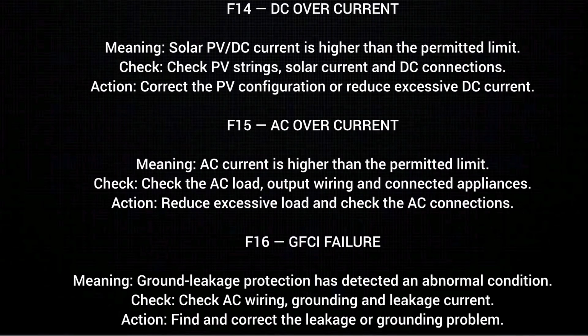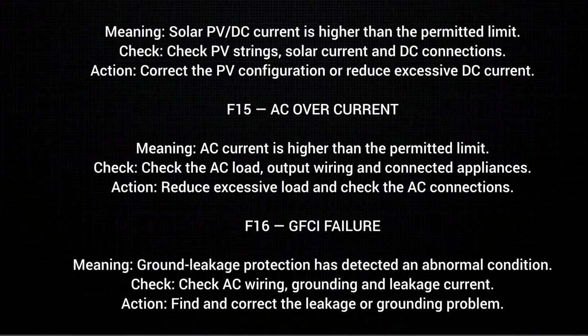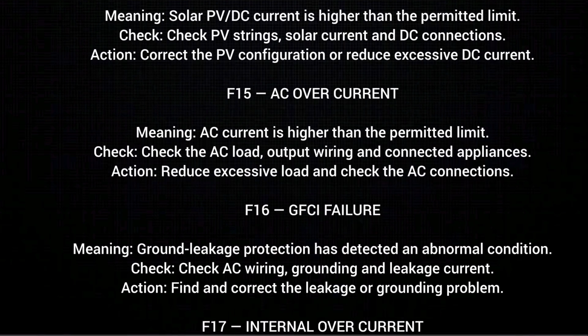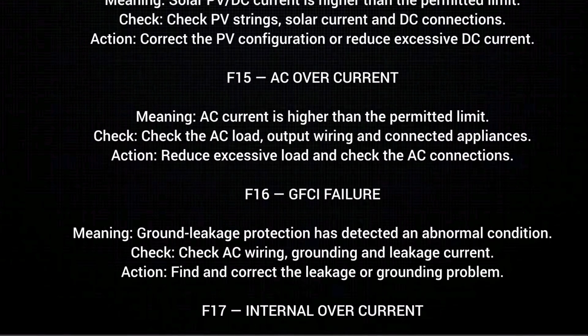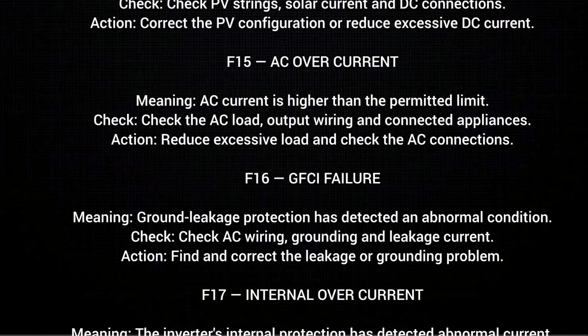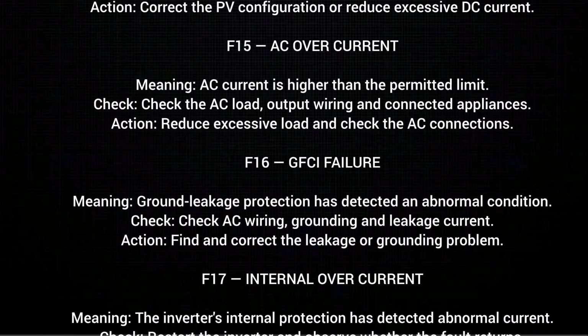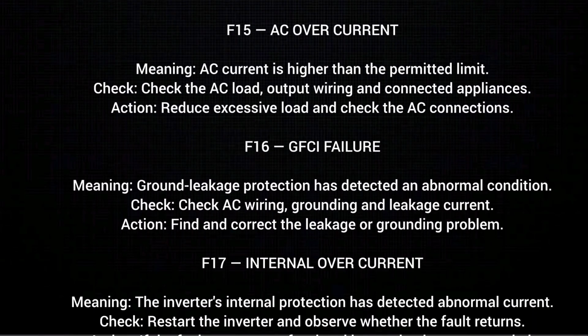F15 AC overcurrent, meaning AC current is higher than the permitted limit. Check. Check the AC load, output wiring and connected appliances. Action. Reduce excessive load and check the AC connection.